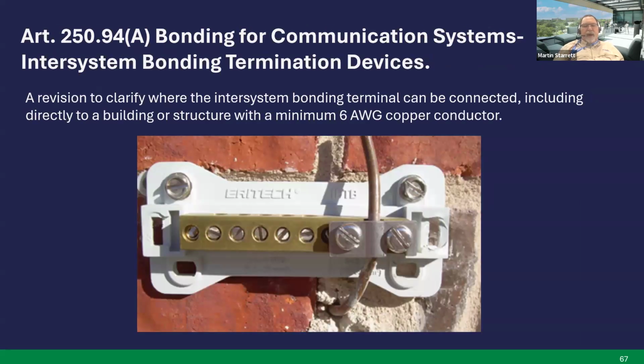Article 250-94A, bonding for communication system, intersystem bonding termination devices. A revision to clarify where the intersystem bonding terminal can be connected, including directly to a building or structure with a minimum 6 gauge copper conductor. They've cleaned up this article. It's a little easier to read, and they have included where you can mount this device on a building. It previously didn't say that, but it does now. It clarifies that you can mount it on a building, but it has to be connected with a number 6 copper conductor. Next slide.